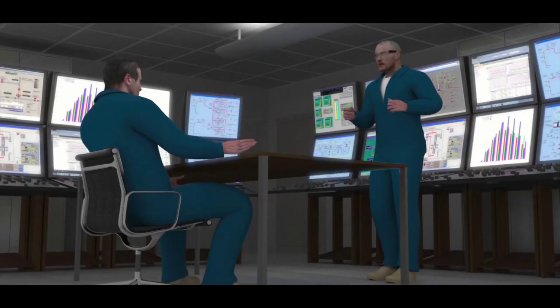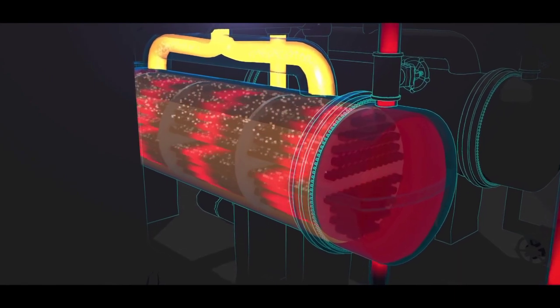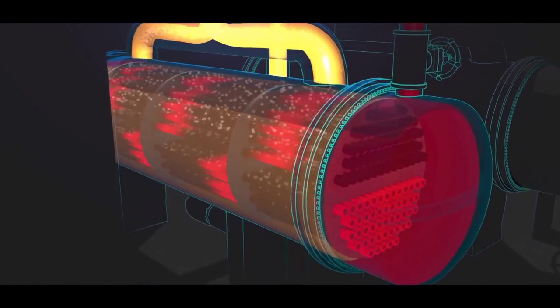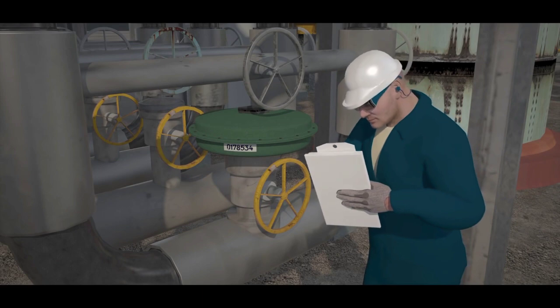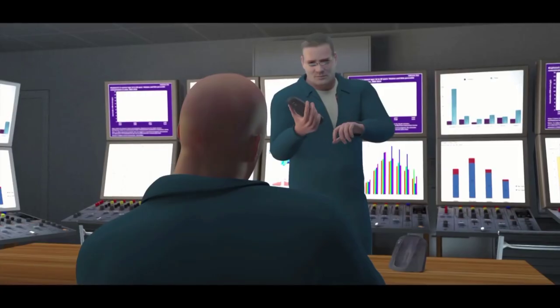On June 13, 2013, during a daily meeting with operations and maintenance personnel, the Williams plant manager noticed that the water flow rate through the operating reboiler had dropped gradually over the past day. The operations supervisor informed the group he would try to identify the problem. He went into the plant to evaluate the water flow rates and informed several personnel that fouling within the operating reboiler could be the problem, and they might need to switch the reboilers.